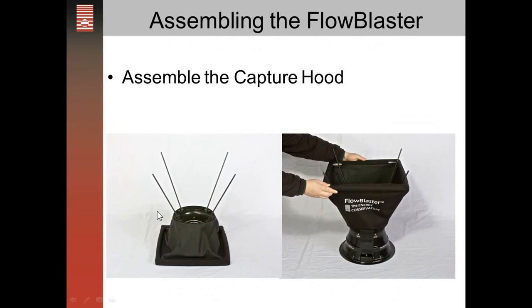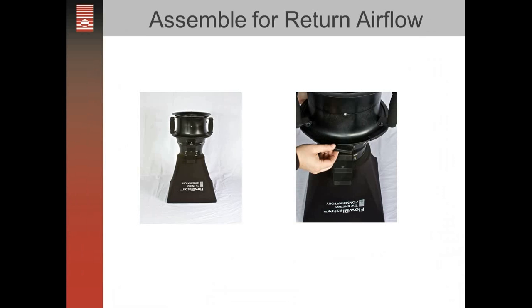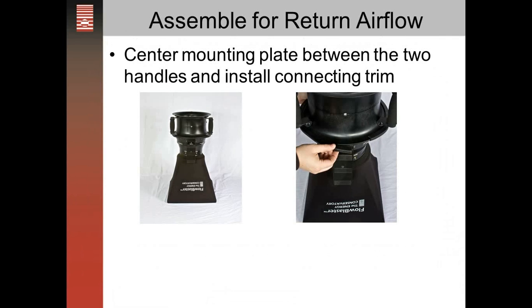To assemble the capture hood, put the four poles down into the pole pockets, slide the hood up over the poles, and there are also pole pockets in the frame around the top of the hood. Make sure those are seated all the way in at both the bottom and the top. To assemble for return flow, center the handles over the gauge board, then put the connecting trim on — the same connecting trim used to attach the flow rings to the duct blaster fan — to connect the duct blaster fan to the Flow Blaster housing.